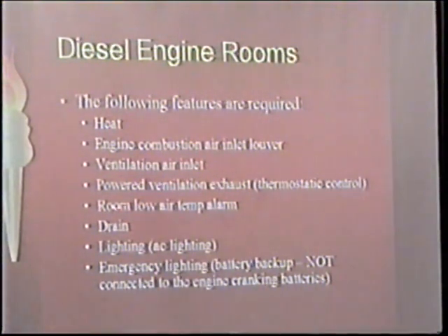the low air temp alarm that was on the new controller for the new diesel. The drain, they decided to drain it back into the reservoir that everything was sitting on top of. The lighting was already there. I'm not sure if the emergency lighting was ever put in, but the heat was there before. But I've been in some of these buildings where there's been no provision for heat. There is no provision for engine ventilation or combustion air makeup.